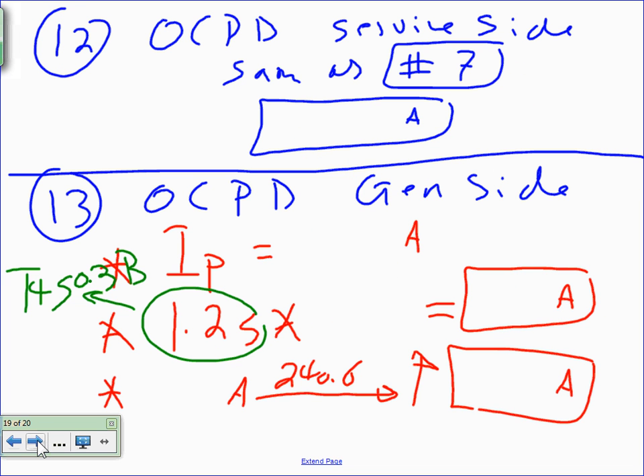Okay, you go to number 12. Now, number 12, guys, is the overcurrent protection device coming out of the utility side. So that would be the same as number 7. And what was number 7? 2000 amp. So here's my question for you. Do I actually need number 7? Most likely you wouldn't need number 7. You just put one at the service, and you do not need step number 7. So that's 2000 amps. But I would like you to get into the habit of sizing it anyway.